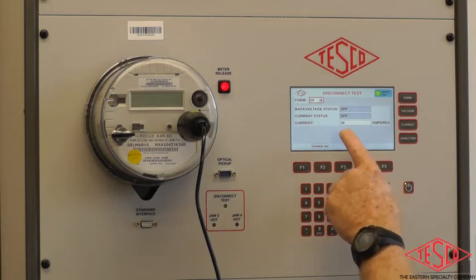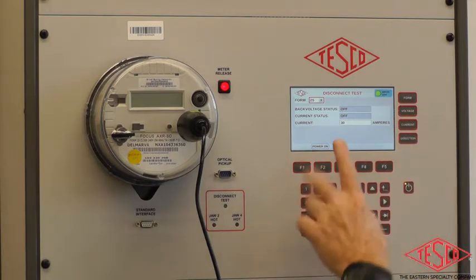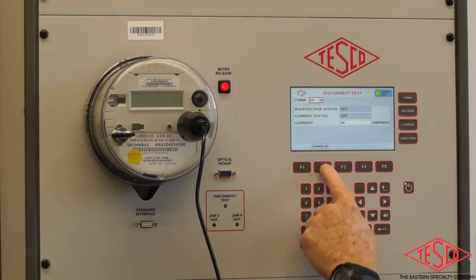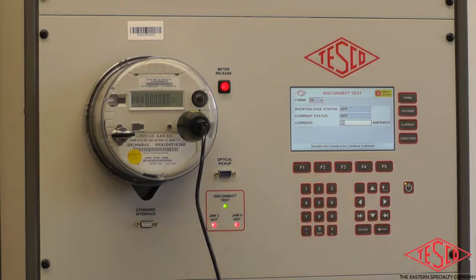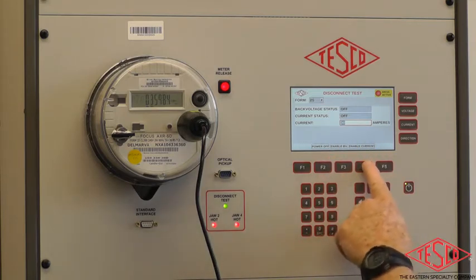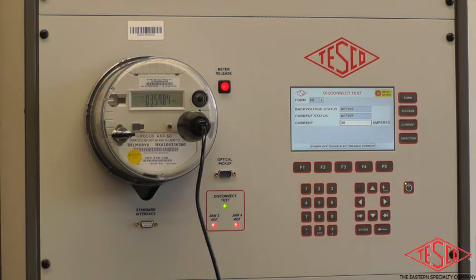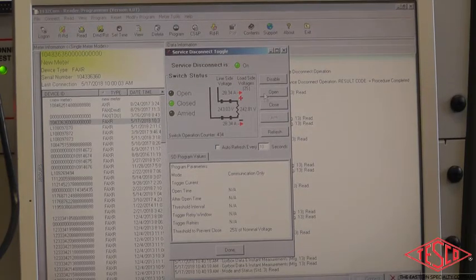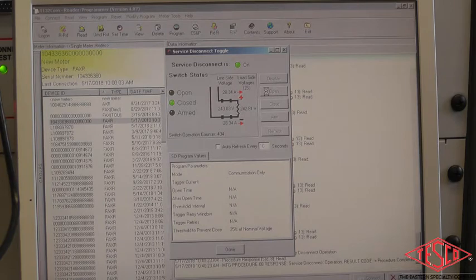The current is set up to be 30 amps already. If you wanted something else, you can press current and change it. This is fine. So power on. Power comes on the meter. And now we're going to establish communication with the meter. So we've established communication with the meter. The state of the back voltage is here. The switch is closed. The disconnect is closed. On the meter, we can enable current, refresh, and verify that there's current on the meter. So we can open the meter with load on the meter, and we will do this via the software here. So we'll go to open.